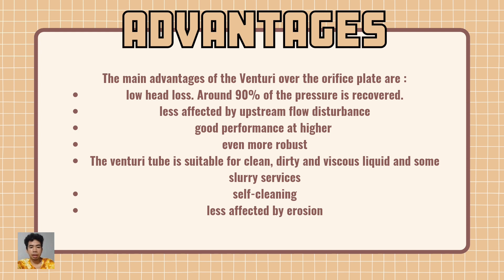2. Less affected by upstream flow disturbances. 3. Good performance at higher flow rates. 4. Even more robust. The Venturi tube is suitable for clean, dirty, and viscous liquids, and some slurry services. It is self-cleaning and less affected by erosion.